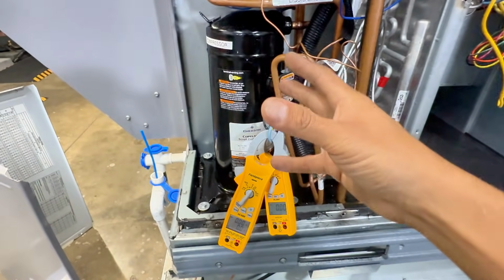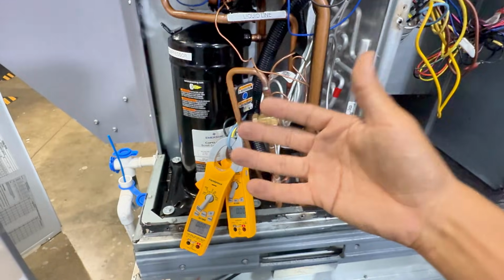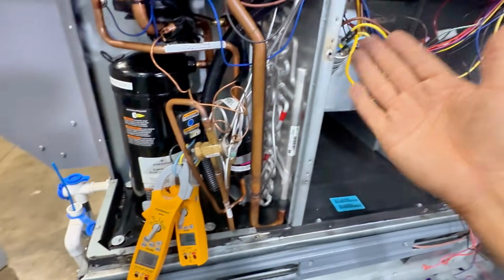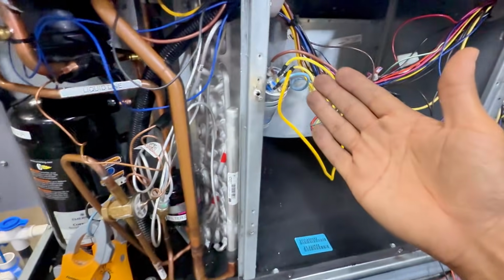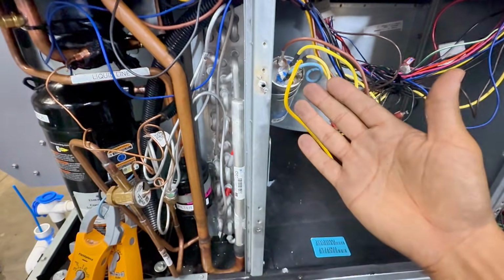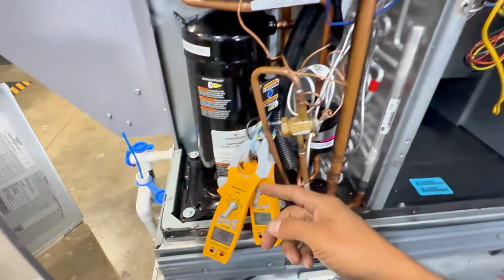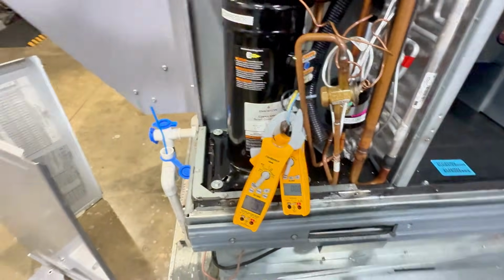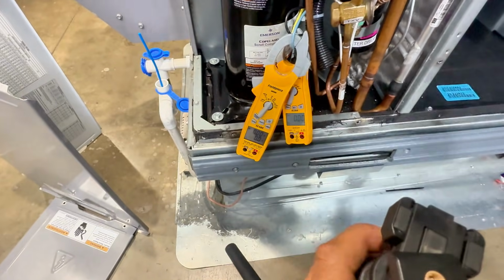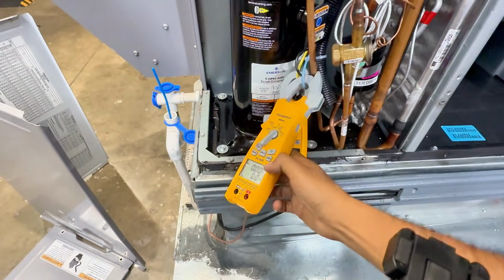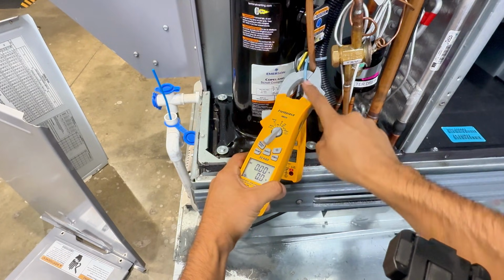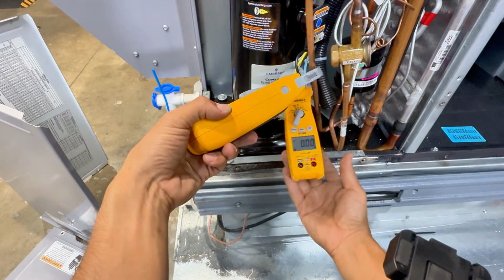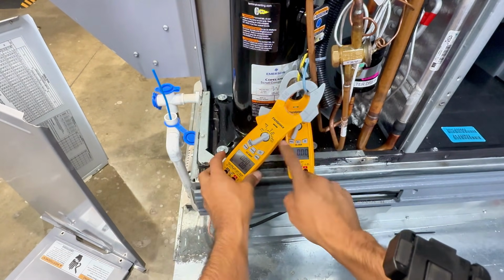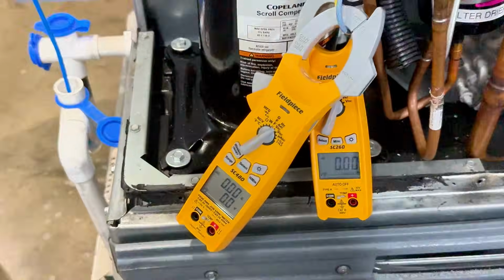Another thing you can do with the compressor is look at locked rotor amps. That happens when you have a weak cap, or you lost all your microfarad reading for your Herm side. But look, when the system is operating right, I'm going to put it so you guys can see. This meter is on your start winding. This one is on my run winding. So start and run. Remember, we have two windings.